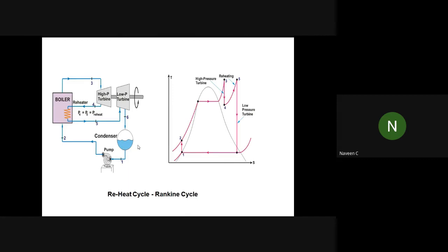That is one thing. And sometimes the water heat can also be used for preheating of the water going to the boiler. There is another important question you may ask: sir, the boiler needs to heat it, so if I give a higher temperature, it will improve the efficiency of the system. Yes, that's why in some cases we will send the water a few degrees above ambient, 4 degrees, 5 degrees like that. But if I say I will send it at 60 degrees, then the pumping load will increase so much, it is also not economical.